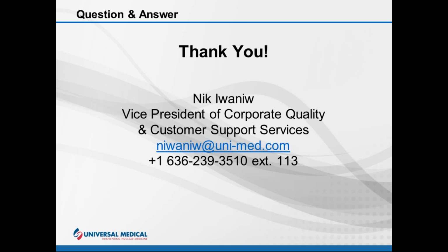Okay, Nick, the first question here: how often do you recommend performing routine preventative maintenance? Well, that's a good question, because generally speaking, preventative maintenance is largely governed by whatever regulatory agency you're under. ACR has recommendations, and a lot of the recommendations are geared by what the OEM dictates, and that's kind of the standard. But most of them, generally, it's every 6 months. That's usually the standard for performing and documenting routine preventative maintenance.